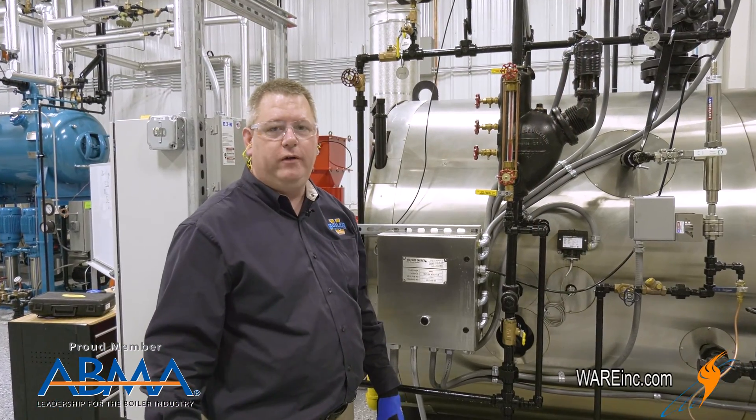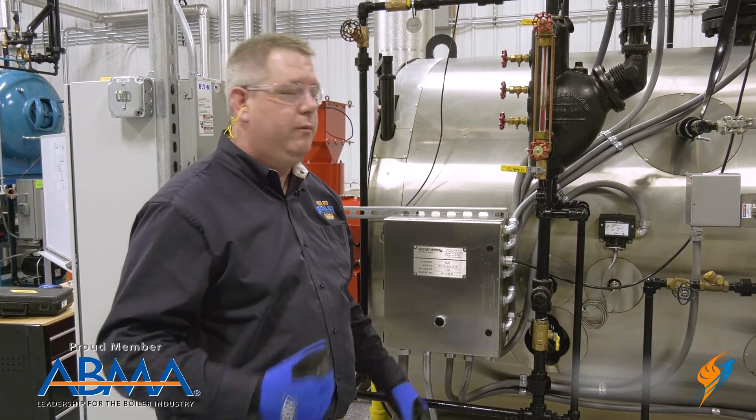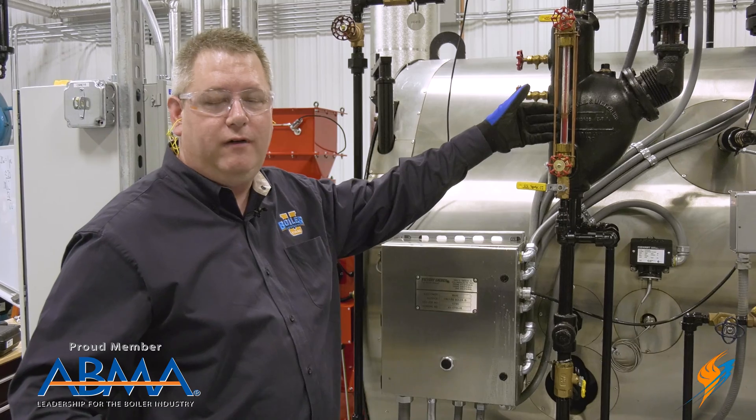Try cocks are not always required by code depending on the pressure of the boiler and the jurisdiction, but they are a great tool — because if we don't have a working sight glass, we're flying blind, and that's not how we want to fire a boiler.